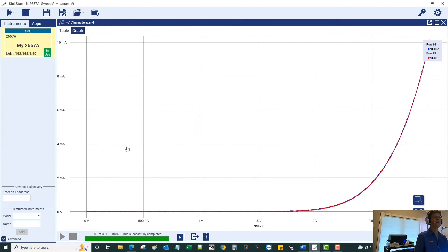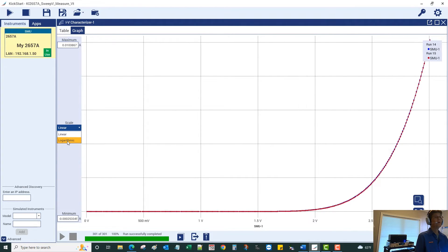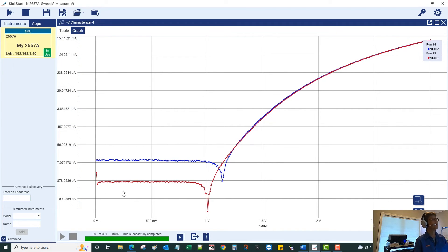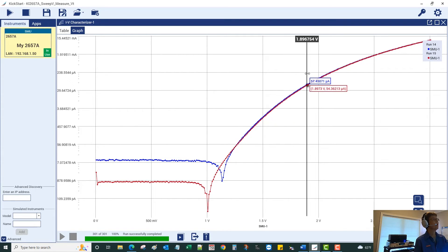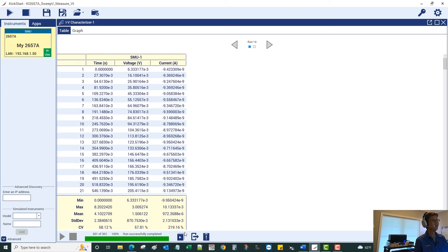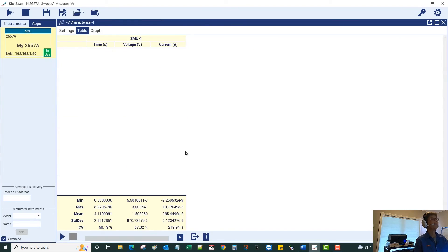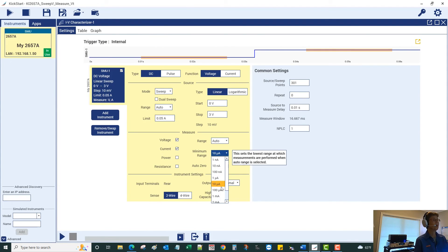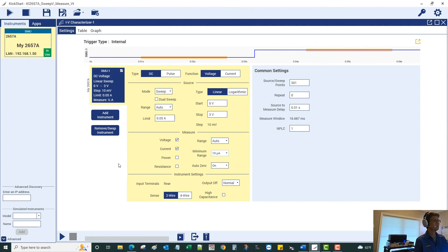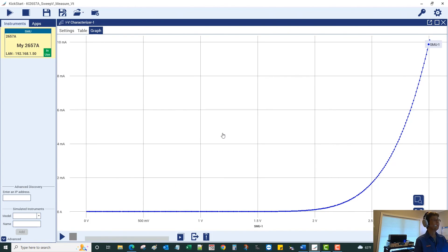Now that it's completed, I'll overlay the two graphs. On the linear scale they overlay very nicely. Switching to the log scale, we can see the difference — run number 15 with the lower current measure range enabled shows low-level values coming in significantly lower, down to picoamps. Whether those low-level values are important to you and worth incurring a little more test time to acquire is up to you. The main trade-off is that as you enable more sensitive ranges, more settling time is typically required to get a good outcome.